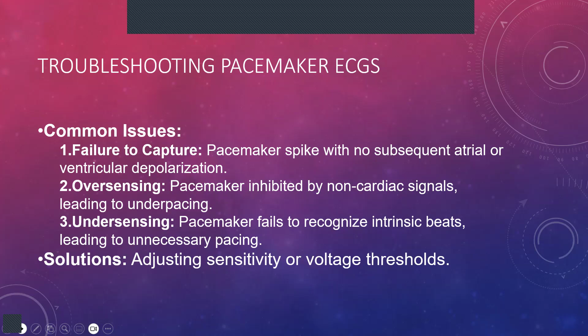And then undersensing, where the pacemaker fails to recognize the intrinsic beats, and it leads to unnecessary pacing of the heart as well. So this normally requires adjustment of the sensitivity and voltage thresholds. This is normally done at a cardiac pacemaking unit. It's not something you can do on your own. There's a specific way that they do it. You know, it's external. There's such lovely pacemakers now that via Bluetooth, they just connect to a computer program. Everything is done. Some of them even have a Wi-Fi connection. There's so many things that they can do to actually make sure that the pacemaker is functioning properly.